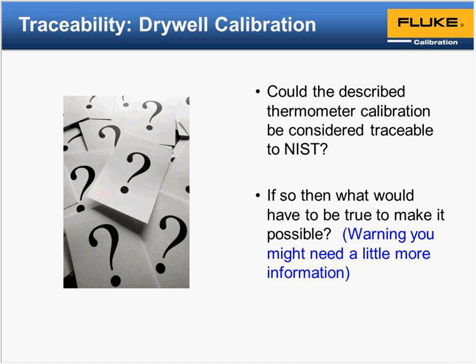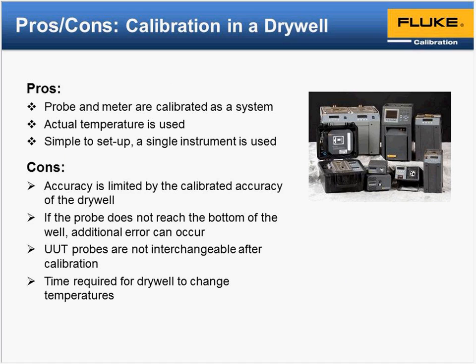If your heat source in this example was calibrated with a traceable calibration, then basically your calibration could be considered traceable because you're just using the heat source now as your transfer standard to the thermometer. So you can prove that unbroken chain through the thermometer to the heat source. The heat source is now calibrated, and I've got supplied documentation with it showing its traceability. If the heat source was not traceable in a particular example, our calibration would not be considered traceable. All right, kind of the real quick pros and cons of the dry well method.